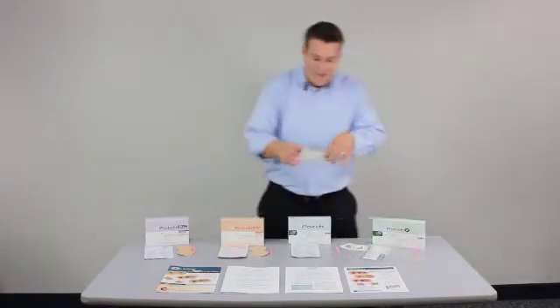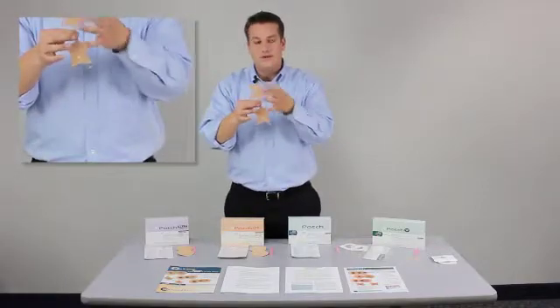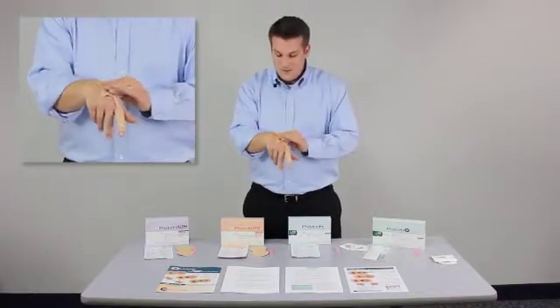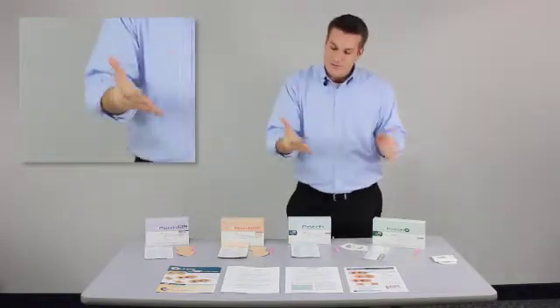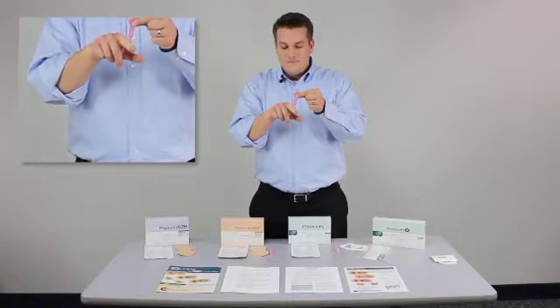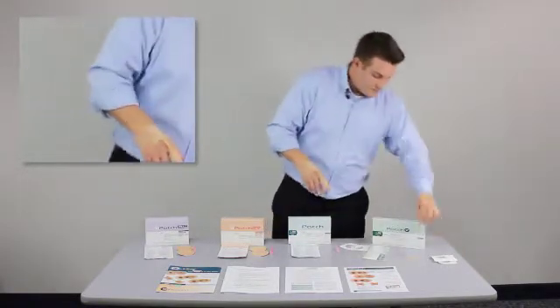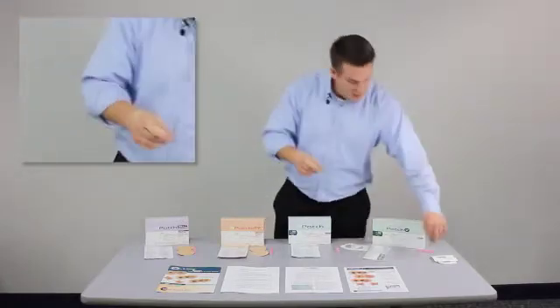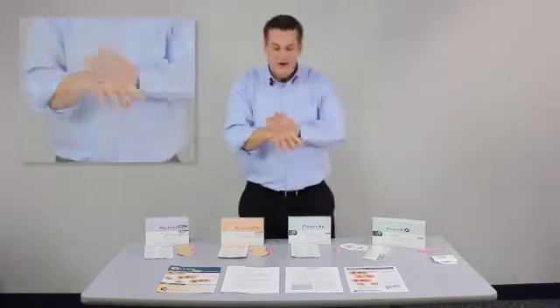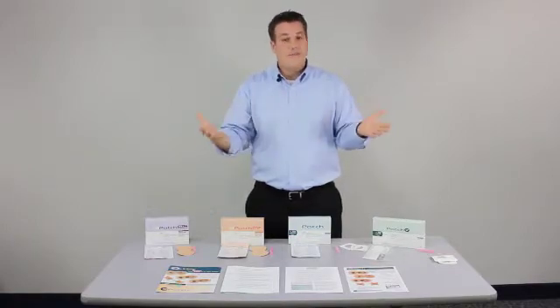The SP application is a little different in that you apply it first and then fill the electrodes through the little porthole covers. If you're treating a finger, apply it to the finger, pull the positive side tight, and make sure you have good skin adhesion. Then take your drug and saline and fill in the little porthole covers — you'll notice it will start to bead up when it's full, and then you know you're done. Do the same on the opposite side. Then take the occlusive porthole covers and apply them over the site to prevent any contaminants from getting into the medicated area — for instance, if a patient needs to wash their hands, this will prevent any solution or liquid from getting into the medicated area.